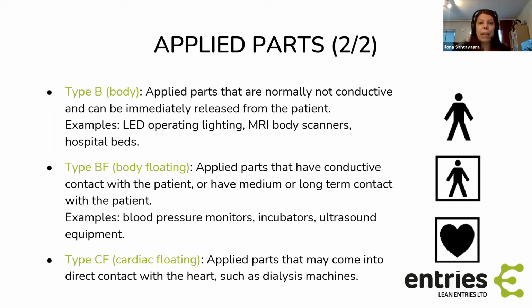So type B, body, is something that's not normally conductive and can be immediately released from the patient. This could be LED operating lighting, MRI body scanners, hospital beds. Type BF, so body floating, is applied parts that have conductive contact with the patient or have medium or long-term contact with the patient. So blood pressure monitors, incubators, ultrasound equipment. And for home use, so if you have defined that you must follow the -11 standard that was for devices for home use, then type BF is minimum for any applied parts. So for those you cannot use the type B. Type CF is cardiac floating, so these are applied parts that may come into direct contact with the heart, like dialysis machines.